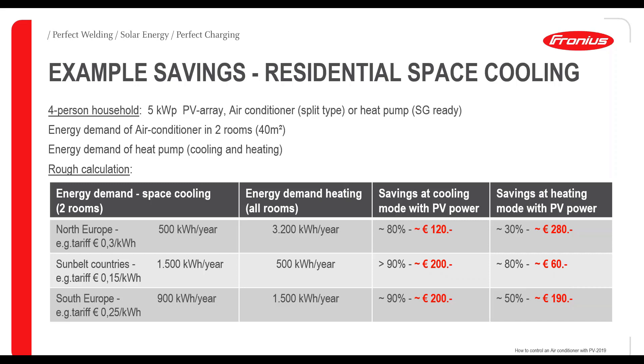The third example is southern Europe with a middle energy tariff of 25 cents per kilowatt hour. Space cooling uses 900 kWh per year and room heating uses 1500 kWh per year. The savings are 200 euros for cooling and 190 euros for heating. Total savings across scenarios range from 260 up to 400 euros per year, achieved just by controlling the air conditioning and room heating loads. Of course, this always depends on the country and where these systems are used.